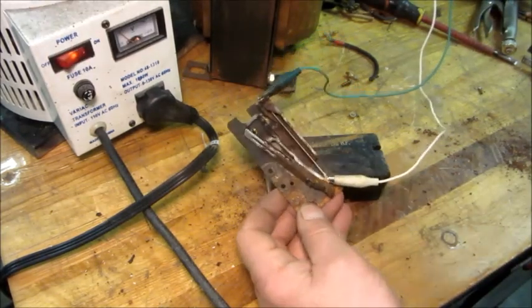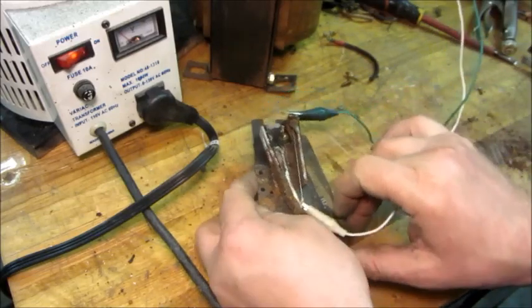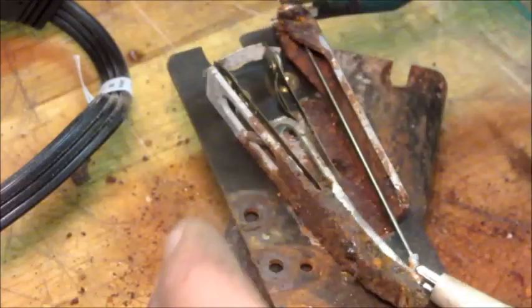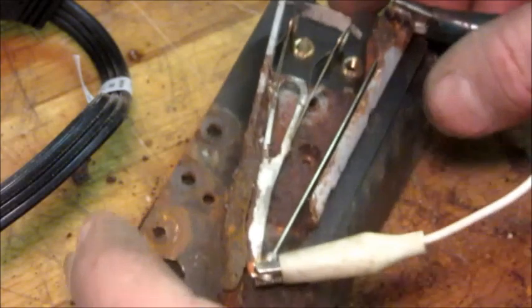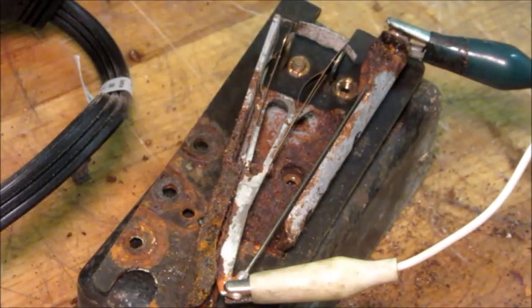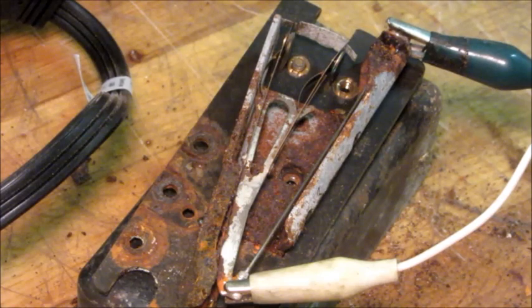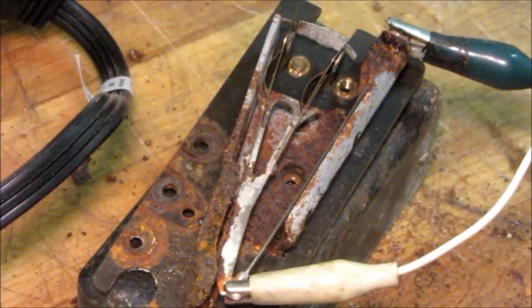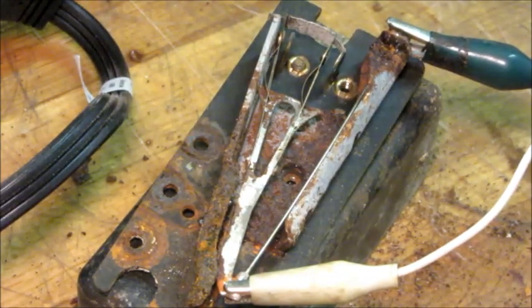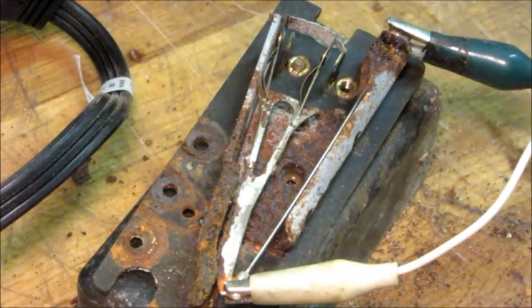I'm going to turn on the transformer. I'm going to set this down so it's right on the screen, zoomed in. These two points here are the overload breaker and the start winding contact. That silver wire is the hot wire that's going to expand — I'm going to start putting current through it now. You see the arm moving? Now the start contact opened on the right. Now I tripped the overload — I went too far with it. If I turn off the current, given enough time that wire will cool off and shrink, and everything will reset.